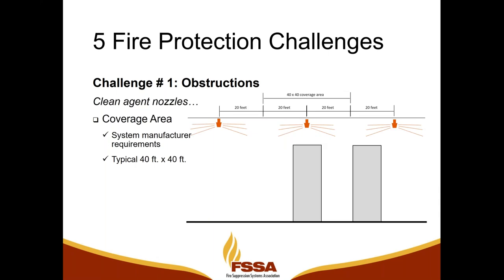It can impact clean agent nozzles. Many manufacturers offer sizing guidelines for how big of an area, how big of a coverage rectangle, a nozzle can cover. In big data centers we would have a typical rule of thumb of a 40 foot by 40 foot coverage rectangle from a single nozzle. If we install aisle containment partitions, that may break up the coverage rectangles, and so we may need to adjust or add nozzles to accommodate those partitions in the space.